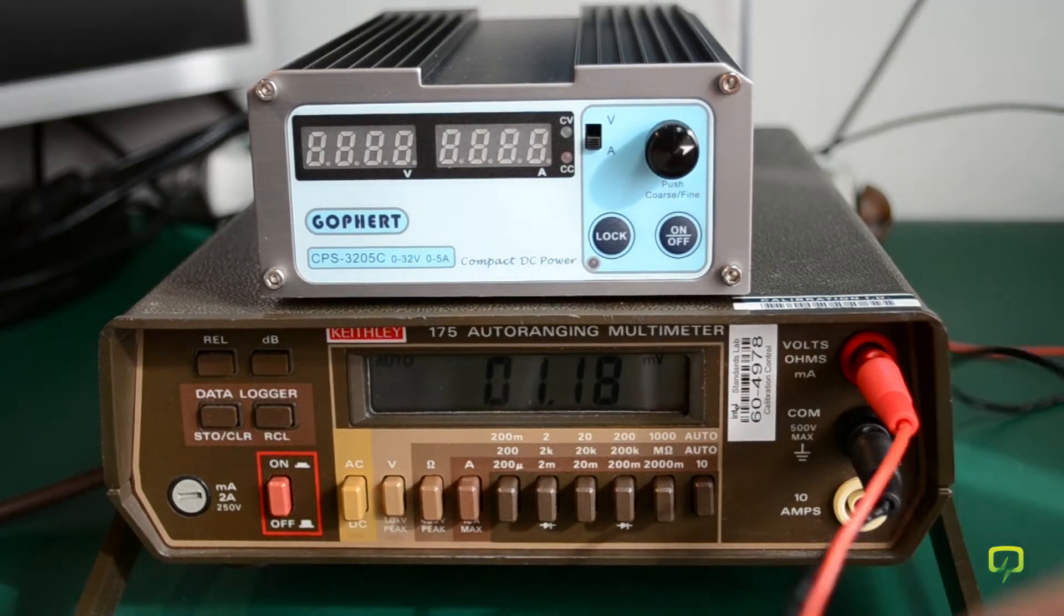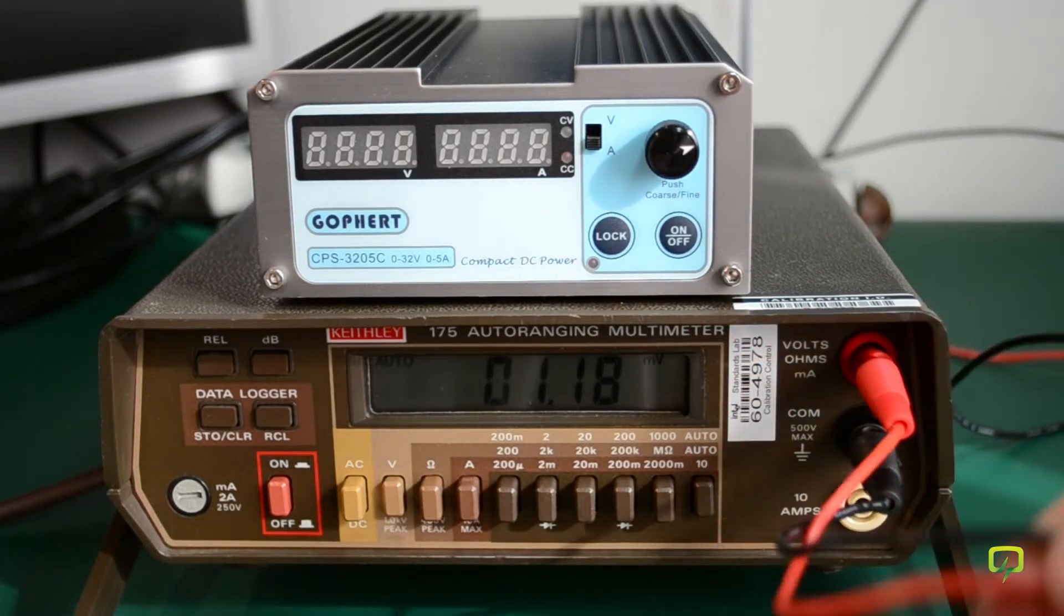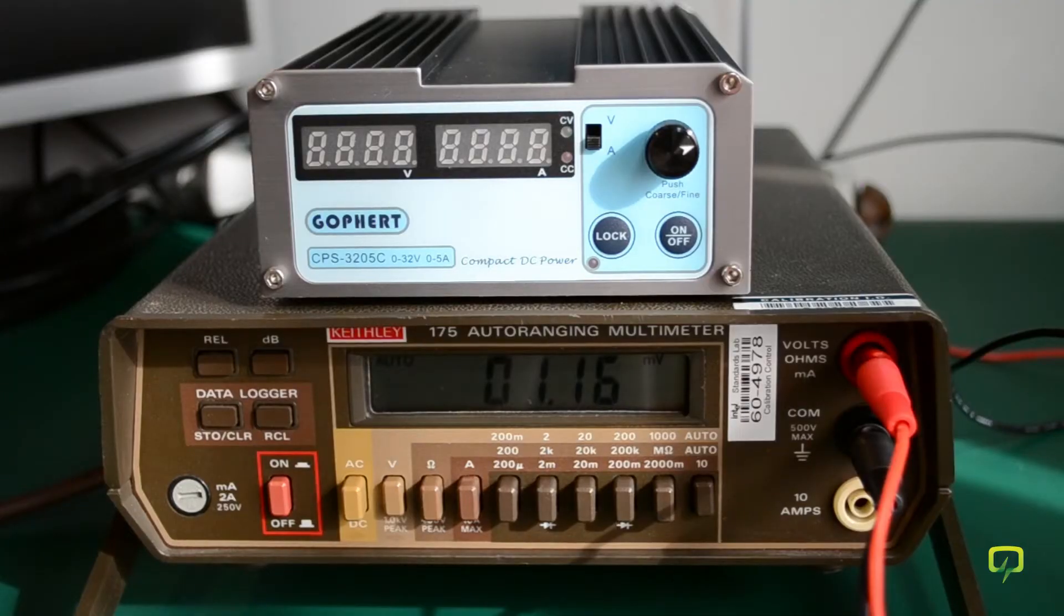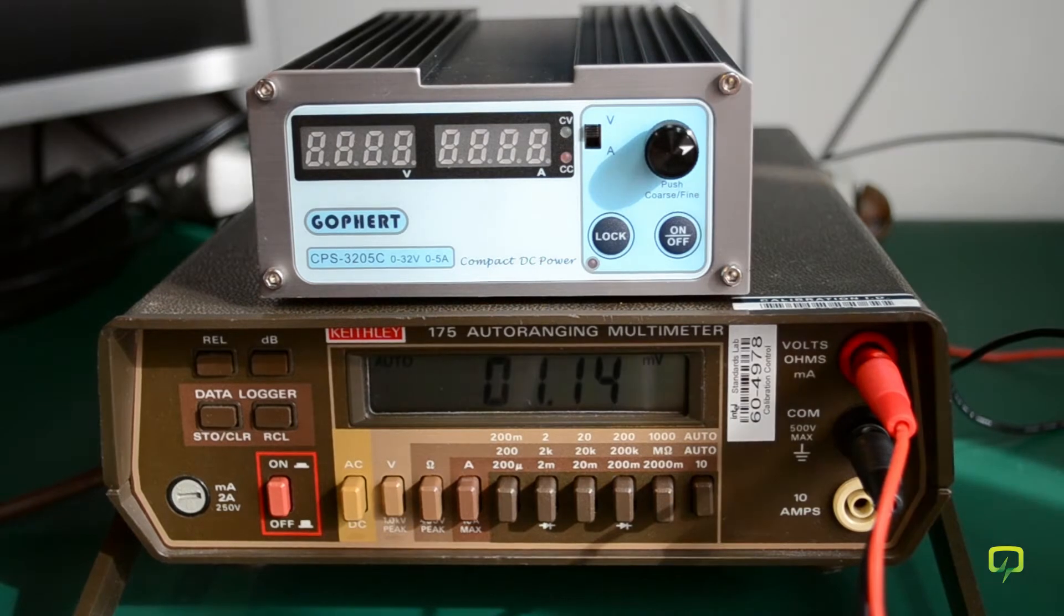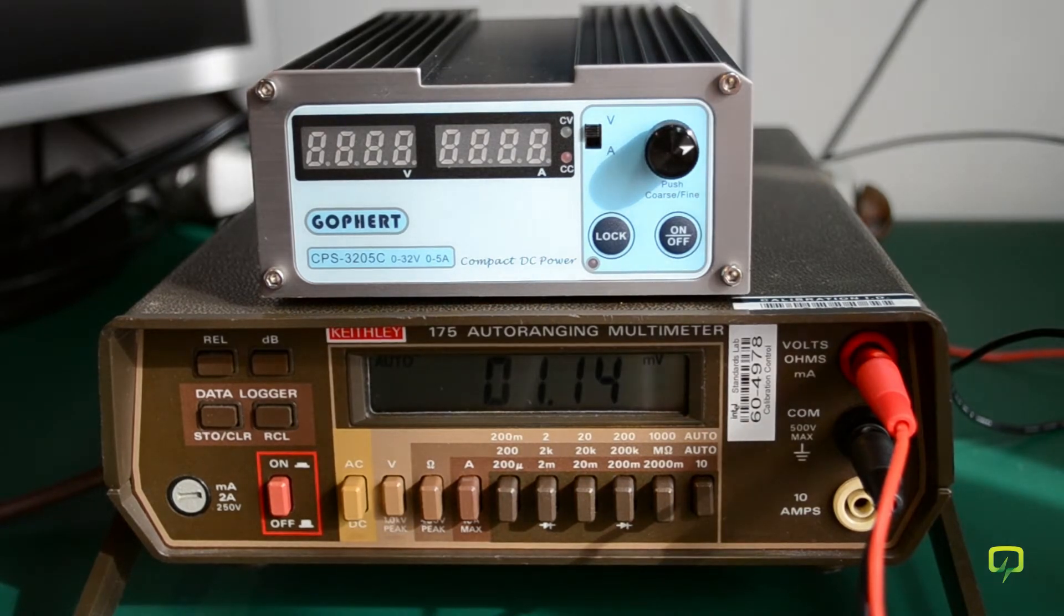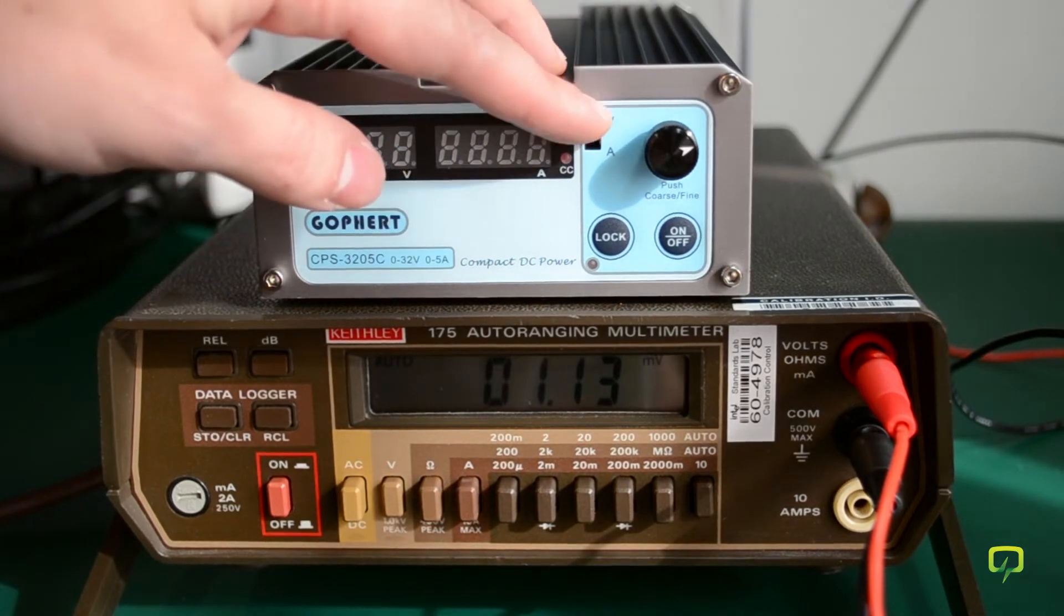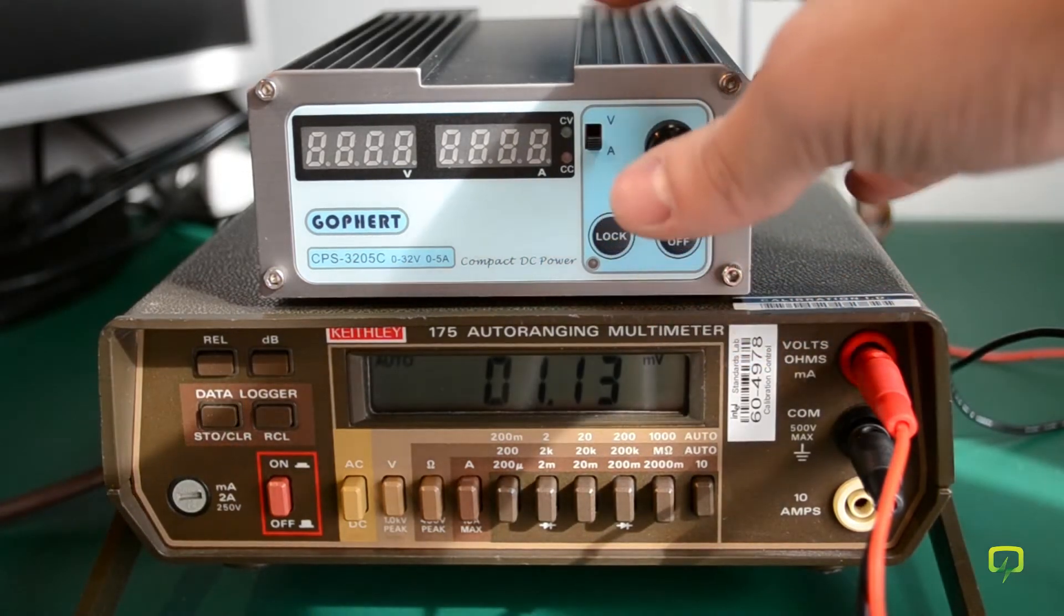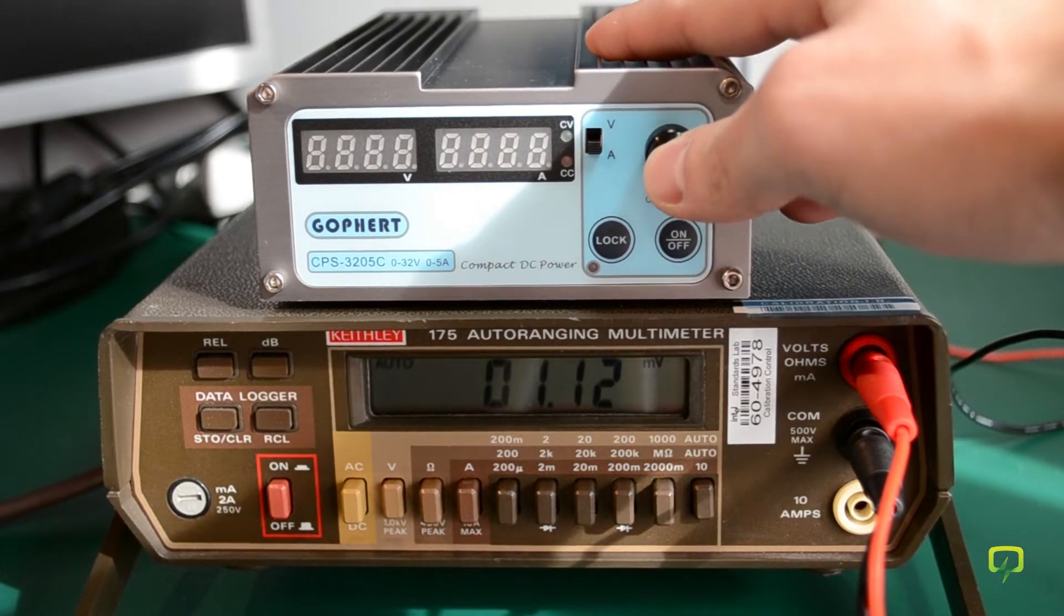So I have my multimeter connected through these leads to the output of the power supply. To enter the calibration, you need to follow this procedure. You set the volts/amps selector switch to the amps position. Then you need to push the adjust knob while turning the power supply on.